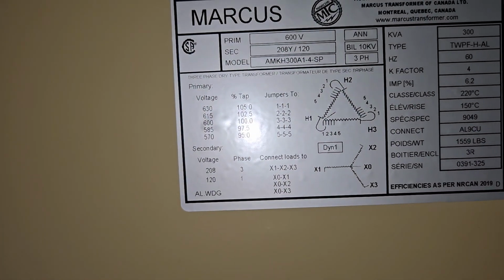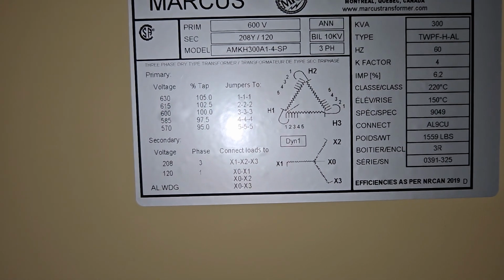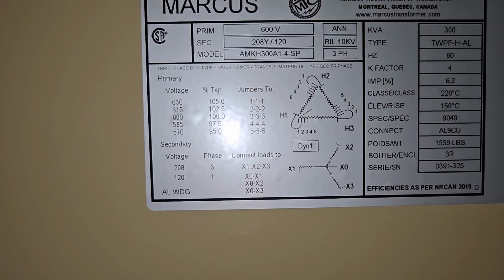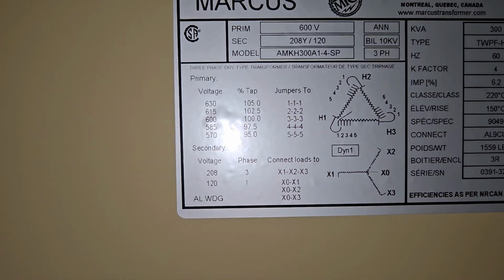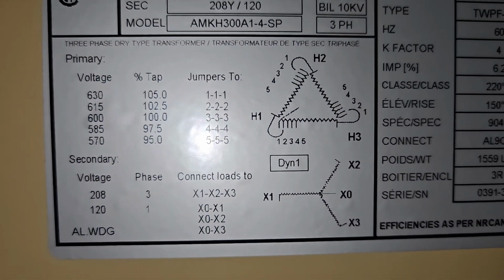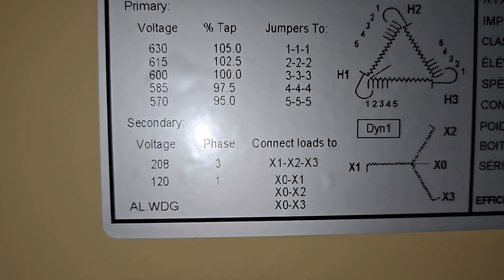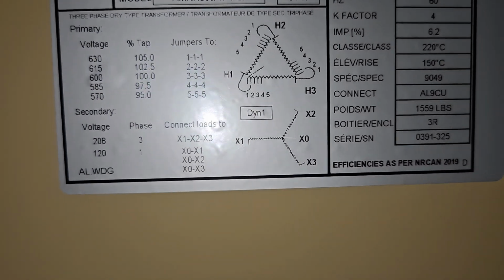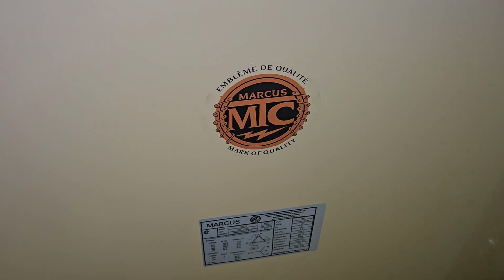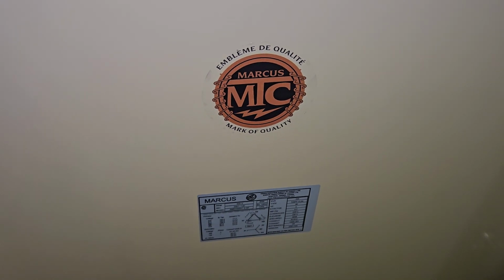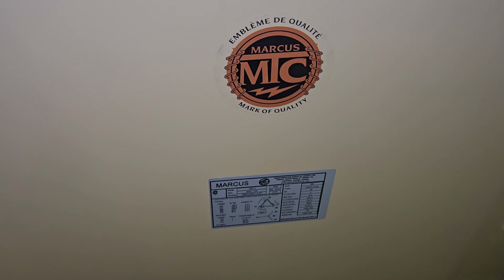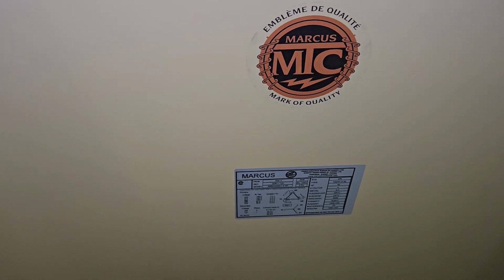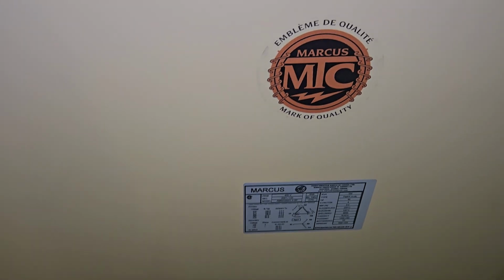But what we want to make sure of is that this thing is tapped correctly. Now your voltage is never going to be perfect anywhere. You're allowed to have a 5% voltage drop between the source and the final amount. So if your voltage drops too much, then you just gotta use a thicker wire.